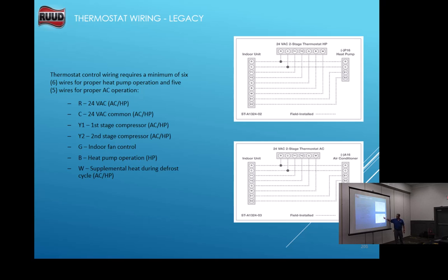They're going to communicate to each other. They're going to talk back and forth. But your thermostat is going to be a regular stat, and that's where you need your 7 or your 6 wires. Okay? But the 2 pieces of equipment are still going to talk back and forth to each other, even though you don't have a communicating thermostat on it. Okay? So, saves you some wire there. All you need are 4 wires going outside for the 15, 16, or 18 SEER communicating equipment. Okay?